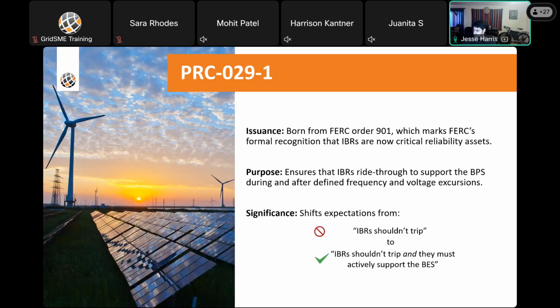So PRC-29-1 was born from FERC Order 901, which was essentially a direction to NERC to develop new or modified reliability standards that require registered IBR generator owners and operators to use appropriate settings. FERC Order 901 had a lot of new standards in it, and PRC-29-1 is just one of those standards under that umbrella. And it's significant because it's the first real formal recognition that IBRs are now critical reliability assets from FERC.